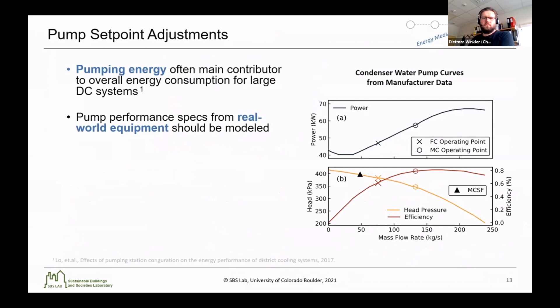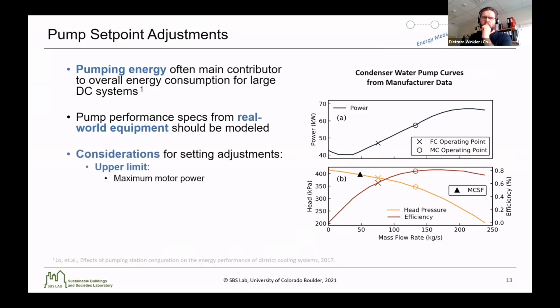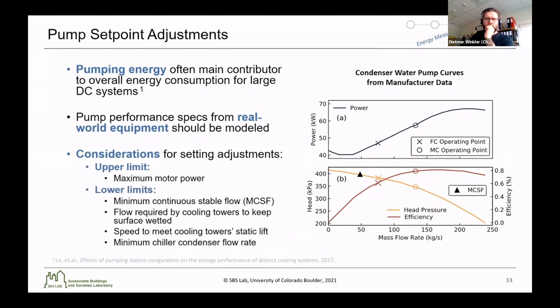We also looked at pump setpoint adjustments, because pumping energy is often the main contributor to overall energy consumption for large district cooling systems. This means it's important to include pumps in the consideration for energy analysis, and also to correctly represent the performance curves for the pumps based on real-world equipment. As an example, I've included the condenser water pump curves from the manufacturer data for this district cooling plant, along with both the free cooling operating point and the mechanical cooling operating point. When adjusting these operating points, there are some important considerations: an upper limit of maximum motor power, and lower limits including a minimum continuous stable flow for the pump, the flow required by the cooling towers to keep the surface wetted, the speed to meet the cooling tower static lift, and a minimum chiller condenser flow rate.